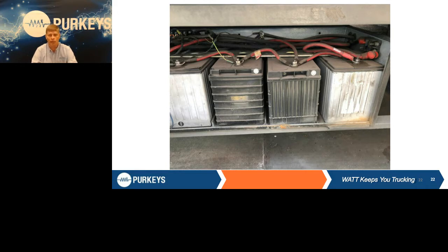You should never mix and match chemical composition, like AGM and flooded cell. They are different batteries. The system will charge either one, but you should never mix them. It doesn't matter if it's a truck or a trailer, you should never mix chemistries. Flooded cells also come in totally different ratings. Our rule of thumb is you should always keep batteries within 50 CCAs of each other and within 6 months age of one another.